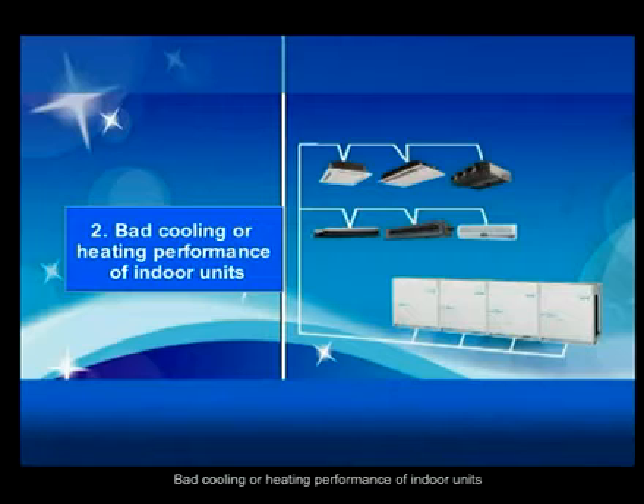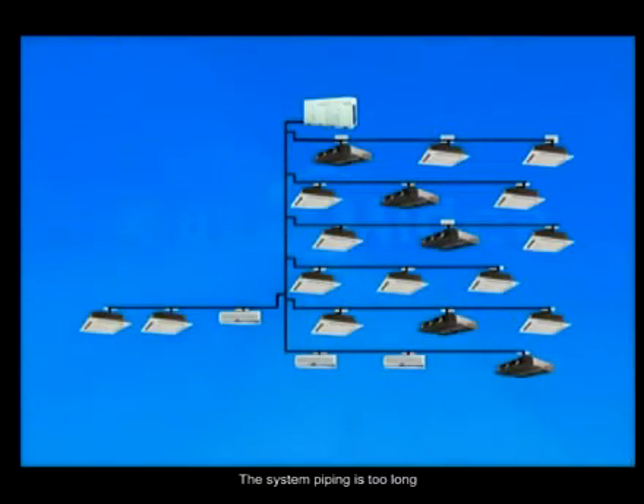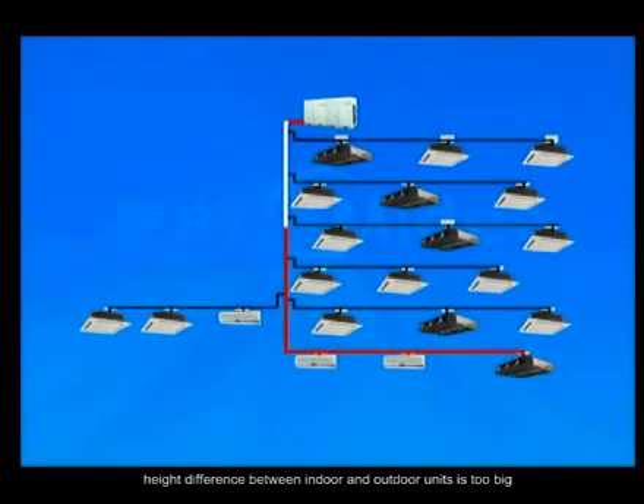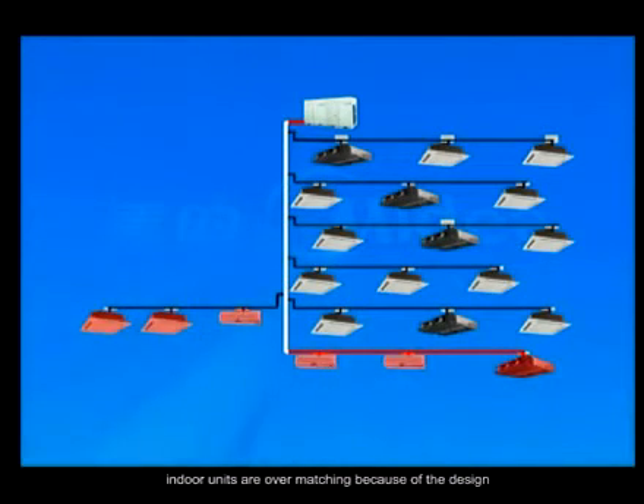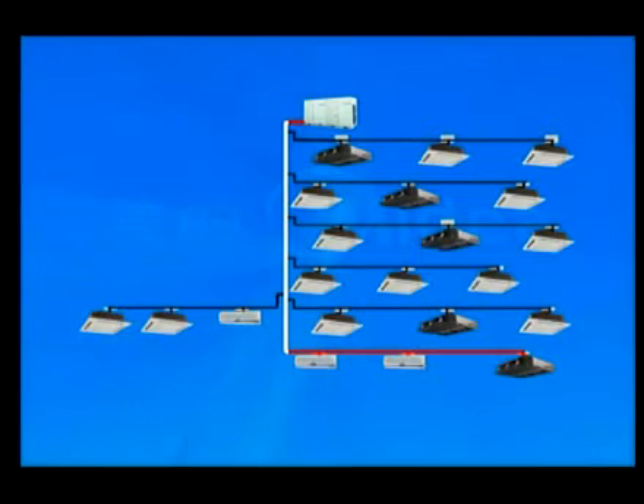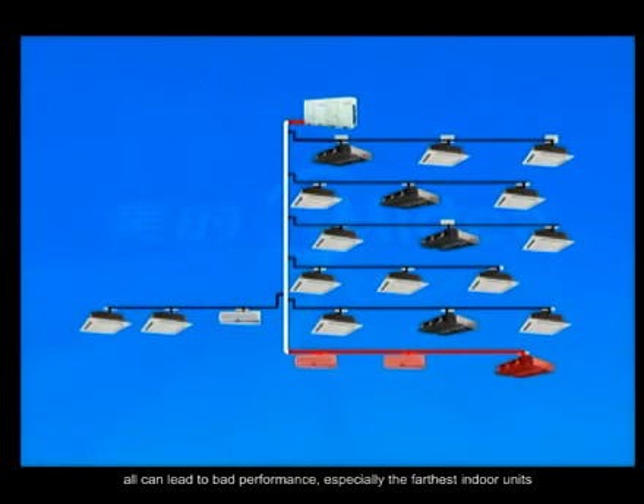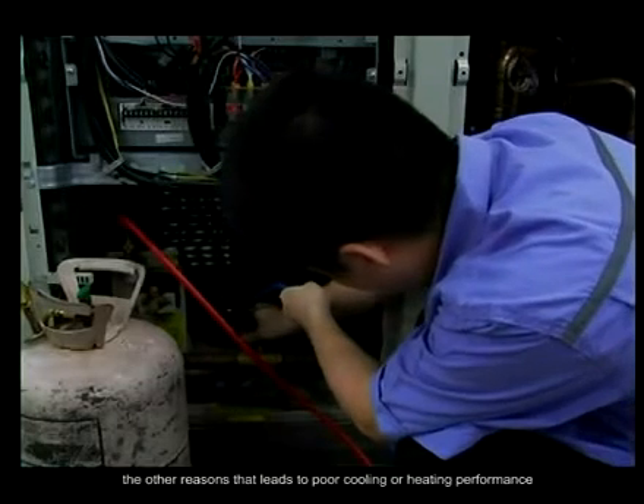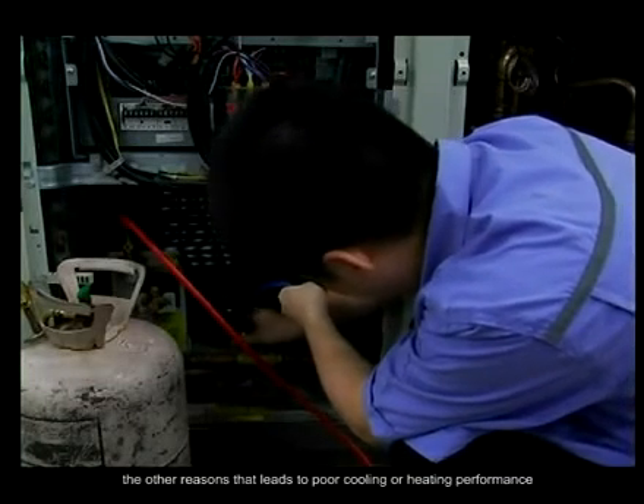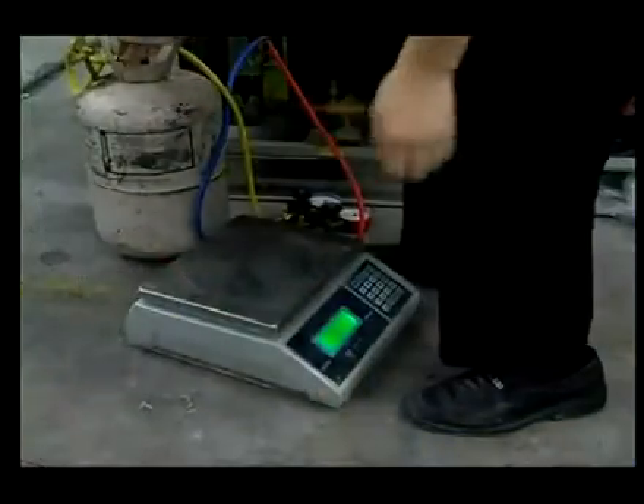Bad cooling or heating performance of indoor units. The system piping is too long, the height difference between indoor and outdoor units is too big, or indoor units are overmatching because of the design. All can lead to bad performance, especially for the farthest indoor units.